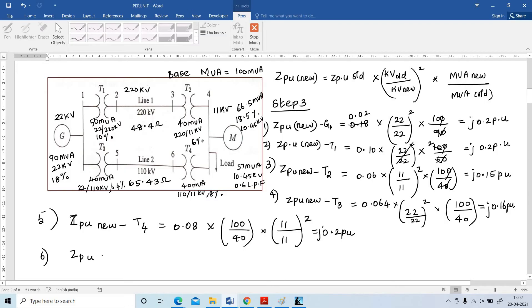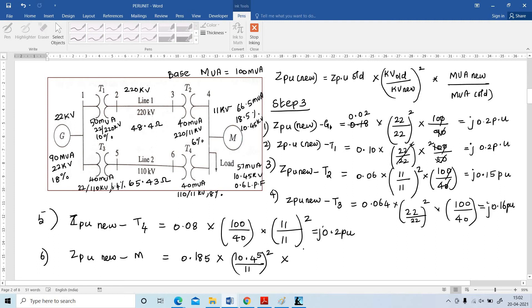Next, ZPU(new) for the motor. ZPU(new) = 0.185 × (10.45/11)² × (100/66.5) = 0.25 per unit.